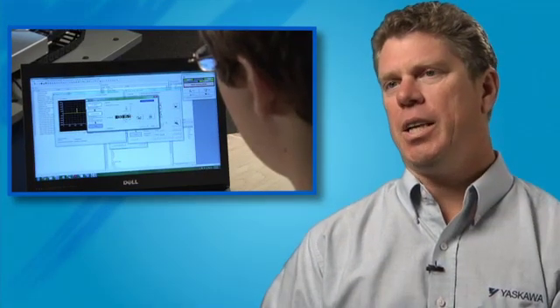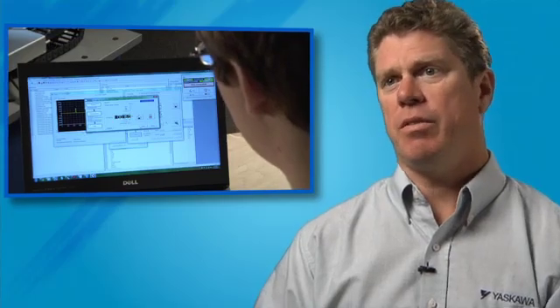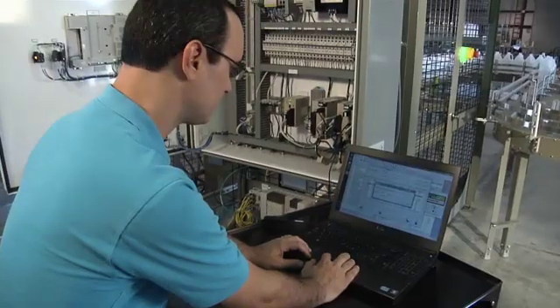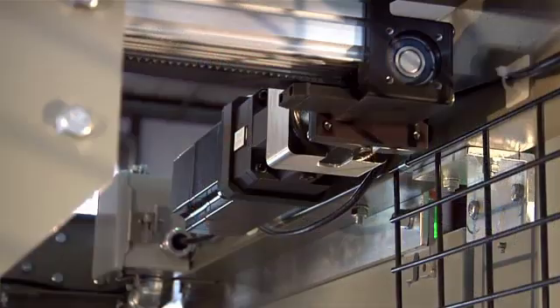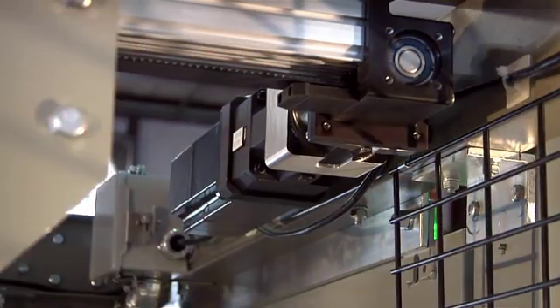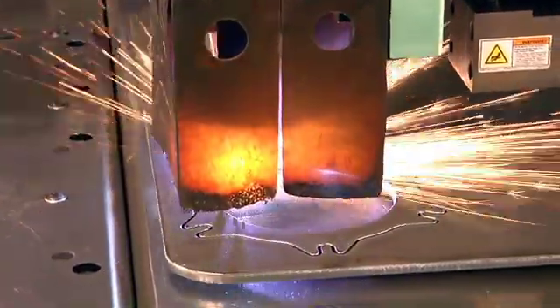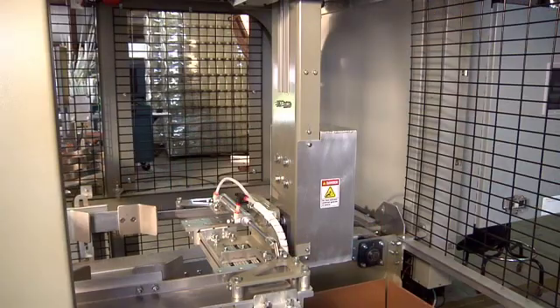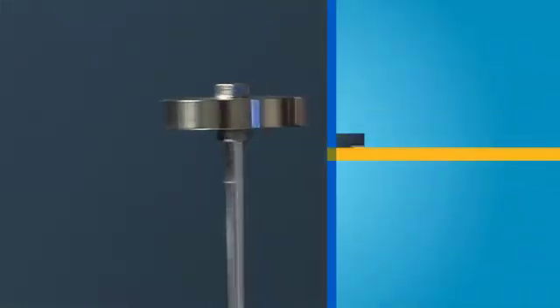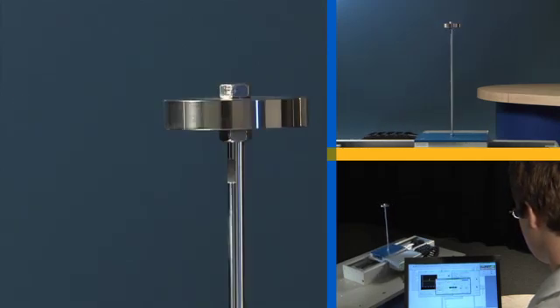So what's unique about Yaskawa's vibration suppression solution is its ease of implementation. With a simple click of a button or auto-tuning wizard, we can automatically detect those vibrational modes with our high-resolution feedback. Just small perturbations and vibrations in the end effector can be seen even through a belt or a ball screw assembly. Once this vibrational mode is found, it's automatically entered into the proper parameter and the vibration is cancelled.